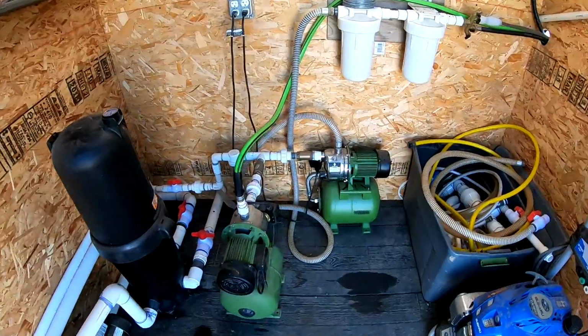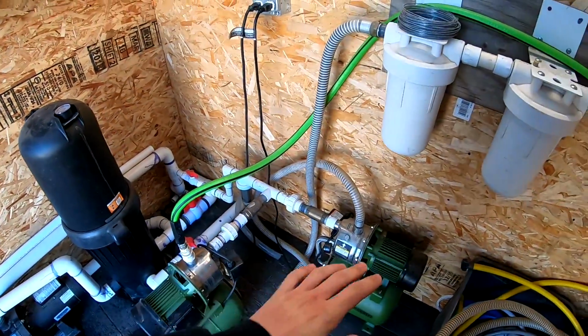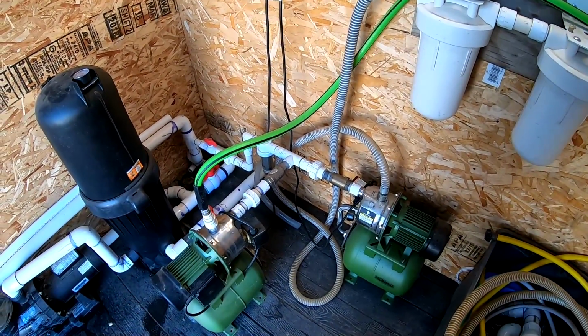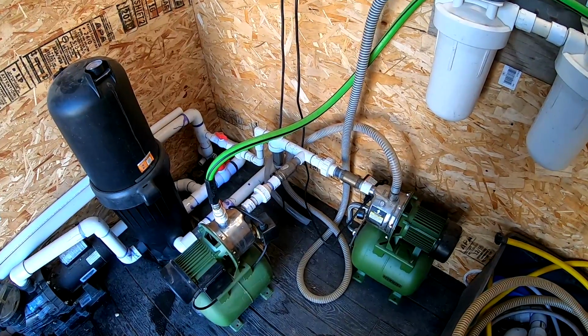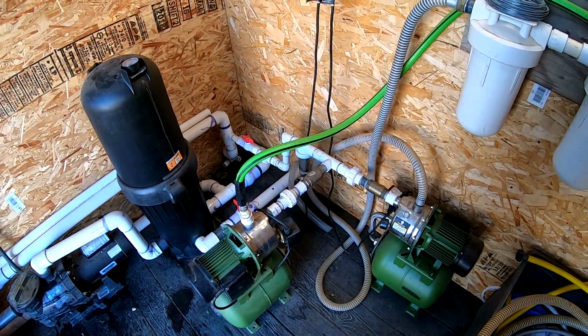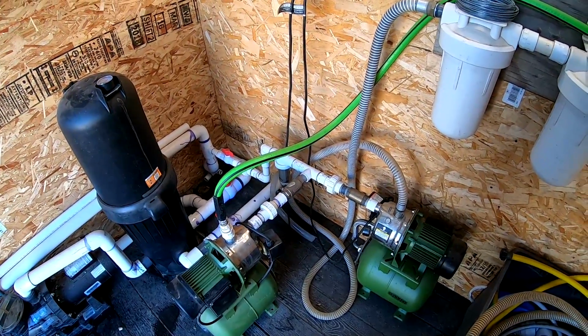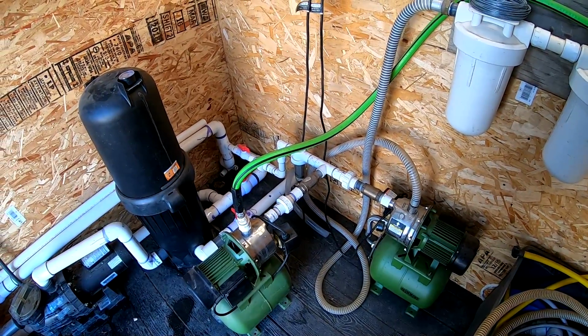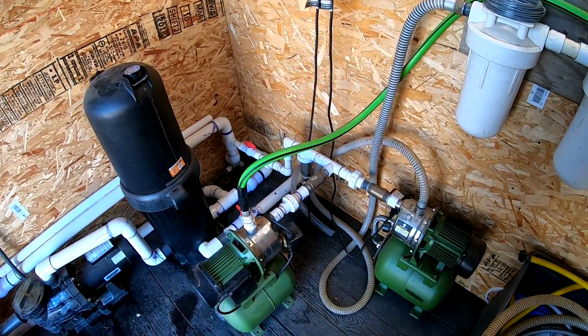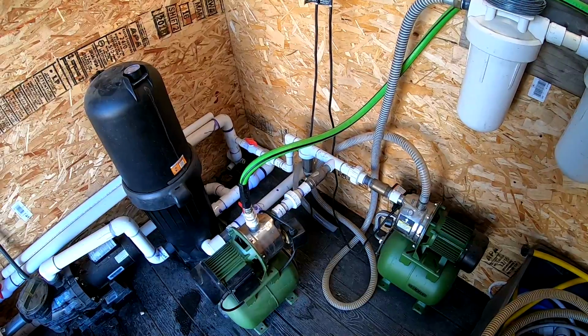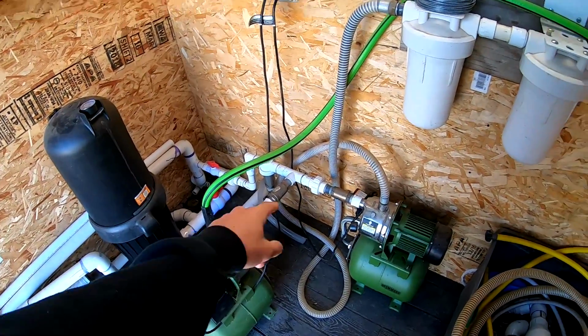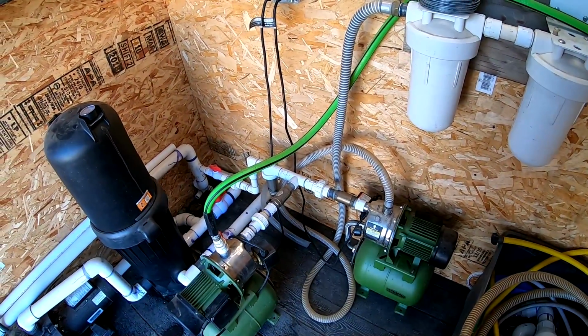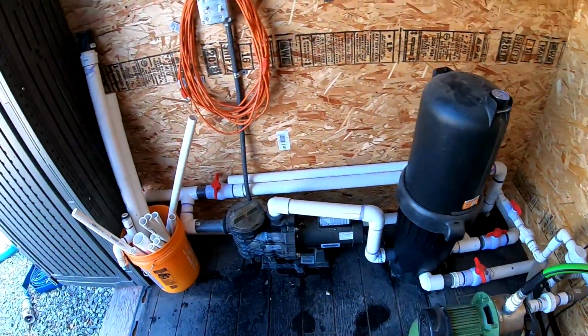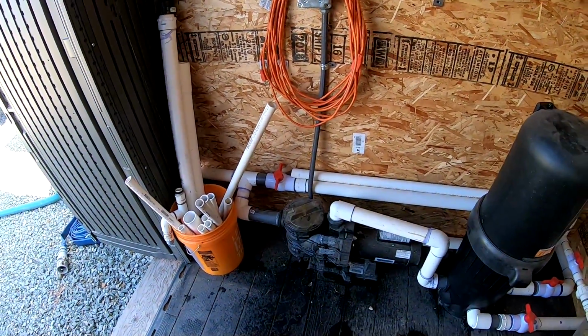And then I do need pressure sensors on both of these pumps, because if for some reason we run out of water, they'll run dry until they burn up. We haven't had that happen yet, but Mom wants to add automatic garden watering, and if that can take place while nobody's here, these pumps can run dry and just burn themselves up. So I'll be adding, like I said, pressure sensors on these pumps tied into the PLC. This pump will be able to be controlled by the PLC.